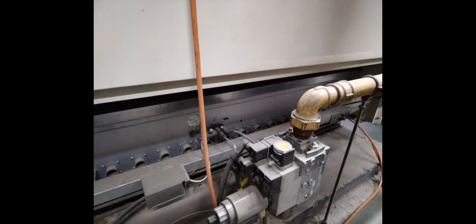Clockwise reduces the pressure and anti-clockwise increases. Once I was happy with my first stage burner pressure, which is here, it's supposed to be 5.8, but I was happy with 5.86. I moved on to my second stage. I've done my low fire over here, just underneath here. You can see there's a groove here on the unit where you can make an adjustment.